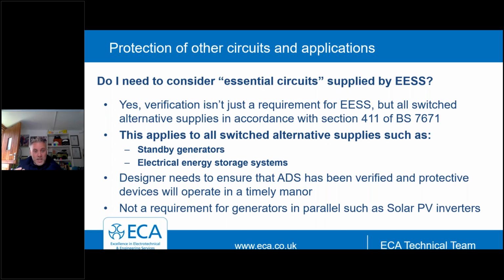So rapid disconnection. Do we get those fault current levels with battery energy storage systems? No, not really. So we need to make sure that our devices will operate. And quite often we need to consider ADS for these and verify ADS. And that's typically where you'll see the addition of RCDs for fault protection to ensure that we still get those disconnection times. So if you are installing electrical energy systems, so battery storage systems, alternative switched systems like diesel generators, for example, the designer should verify that the protection's still going to work either on raw mains or on alternate load. And we've got some great forms we've just developed here at the ECA, which take into account switched alternate sources. So you can document your switched alternate source, and then you can verify your ADS measures, and you can accompany that with your electrical installation certificate. So that is a requirement. As we said, this isn't a requirement for parallel sources such as solar PV.